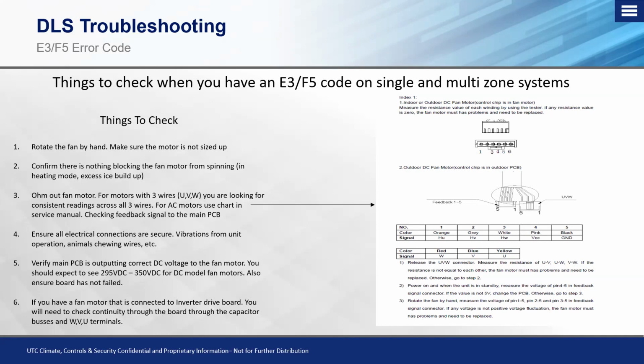So again, making sure all the electrical connections are secure, shutting the power off, waiting 5 minutes, letting the capacitors discharge for the DC bus, and then going through and checking every signal connection on the board to its individual mechanical component. Now, in this case, we're troubleshooting the fan motor, so we just need to make sure that the Molex plug connection going to it is secure, nothing's broken loose, give the wires a little bit of a wiggle, and then also check the male to female connectors on the main PCB that are associated with that outdoor fan motor.